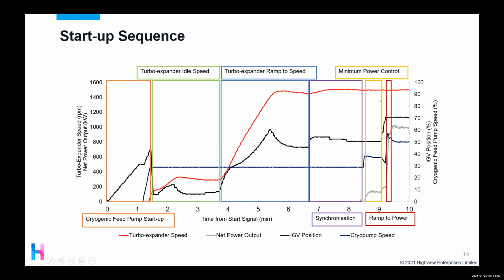And at this point, we can move from minimum power control to a power ramp. So we start ramping up the turbine now to a higher set point. Sorry, the cryopump, I should say. We start ramping up the cryopump speed to a higher set point, and this puts net load into the grid. And then we ramp up both the IGVs and the cryopump speed to provide a higher net output onto the grid. And this, in this particular scenario here, is about 1 meg, and this will keep ticking away until we get the signal to stop, or we decide to stop, or we run out of fuel.